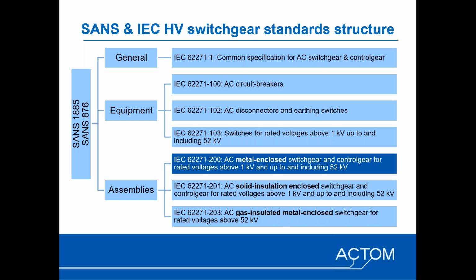And then, for example, there's other standards such as the gas-insulated metal enclosed switchgear for high voltage applications, so above 52 kV. Maybe just worth noting that -200 metal enclosed switchgear can cover all the different types of architecture, including GIS. So there's no dedicated gas-insulated metal enclosed switchgear standard for medium voltage. They're all covered effectively by -200.